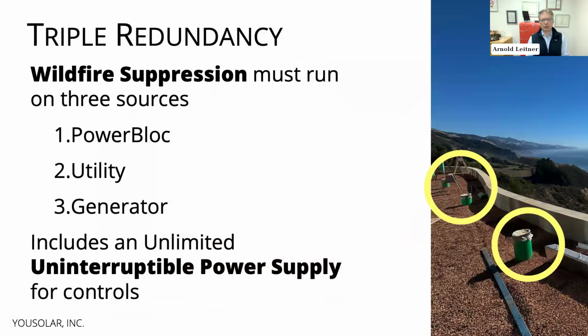Getting back to triple redundancy, on the right-hand side you see these green pipes, that's the fill, or takeout, of the wildfire suppression system. There are some 8 tanks or so buried here, and this required triple redundancy. The primary power of the house is of course the PowerBloc, but if it were to go down, utility power would come in. If utility power wasn't available and the PowerBloc wasn't there either, then the generator, which also feeds the PowerBloc, would transfer over and drive these pumps.